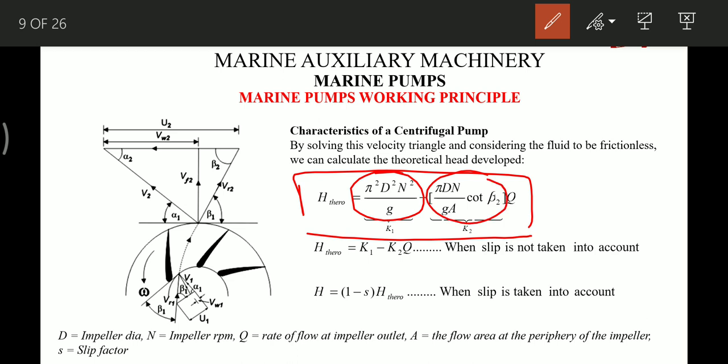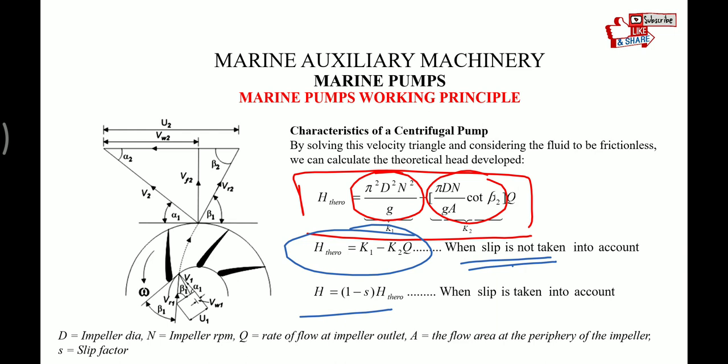The final equation is: H_theoretical = k1 − k2·Q, which is a straight line with a negative slope. This equation does not yet consider the slip factor. If we include the slip factor, the equation becomes: H = (1 − slip factor) × H_theoretical.